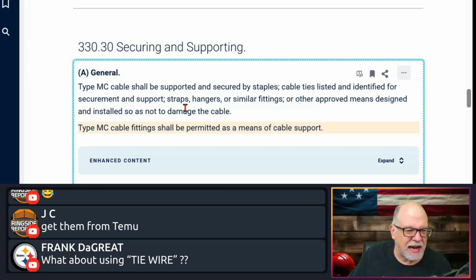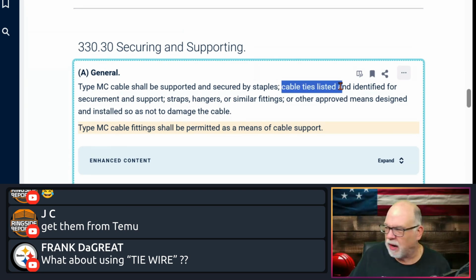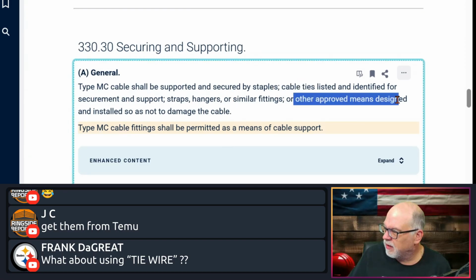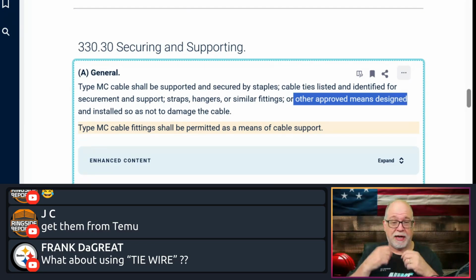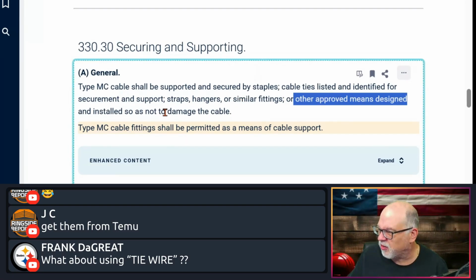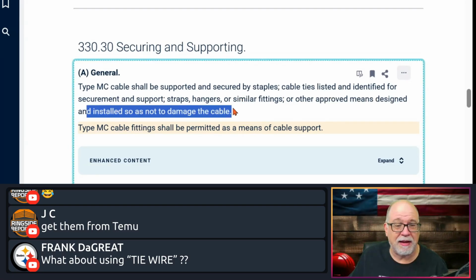What about using tie wire? Frank, right here, cable ties. You just like a tie wire. Well, that one's going to be right here. Other approved means. So if your AHJ is perfectly okay with a tie wire, right? I don't have a problem. Installed such that it's not going to damage the cable. I don't have a problem with a tie wire.